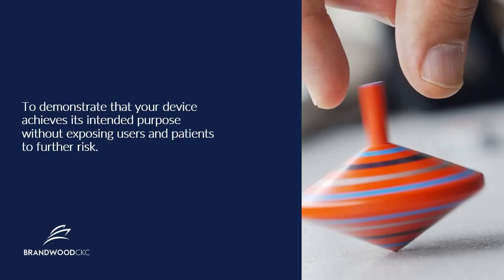The main purpose of a CER, or a clinical evidence report, is to demonstrate a positive risk-benefit profile of the medical device. It supports the clinical safety and efficacy of the device and ultimately is used to demonstrate conformity with the relevant general safety and performance requirements in Europe, as well as the essential principles in Australia.